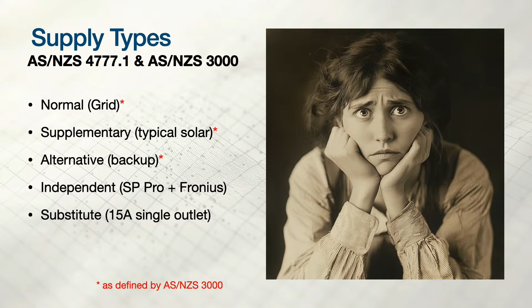Now I'm going to turn my little face off so we can see a bit better. Let's talk about supply types. We used to just talk about normal supply and solar supply or inverter supply, but now we've tried to harmonise with AS/NZS 3000 and use the terminologies already in 3000. The ones I've put an asterisk next to are terminologies used in 3000, such as grid, supplementary and alternative, and we've added a couple of extra ones: independent and substitute. It seems a little complicated, but it flows through to your labelling of main switches and any documentation - you need to use supply type names correctly.